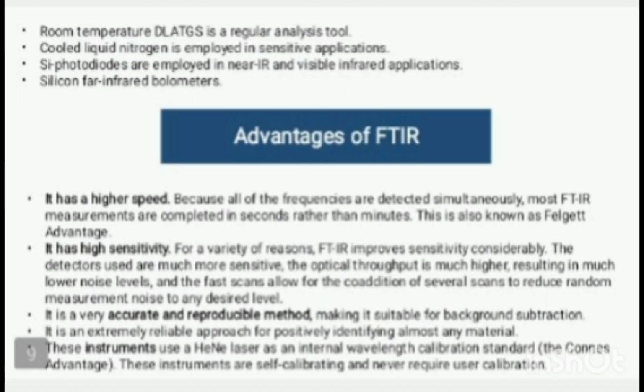Cooled liquid nitrogen is employed in sensitive applications. Silicon photodiodes are employed in near-infrared and visible infrared applications. Silicon far-infrared bolometers. Next one is the advantages of FTIR. FTIR has a high speed because all of the frequencies are detected simultaneously. Most FTIR measurements are completed in seconds rather than minutes. This is also known as the Fellgett advantage.